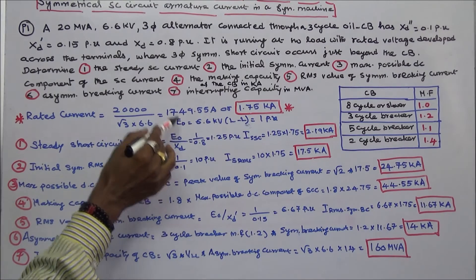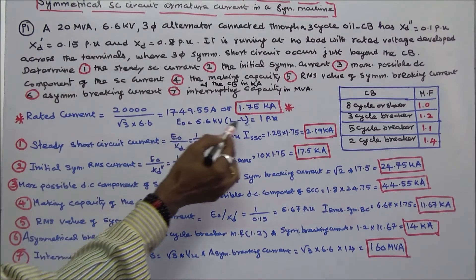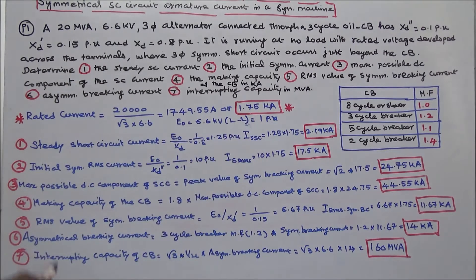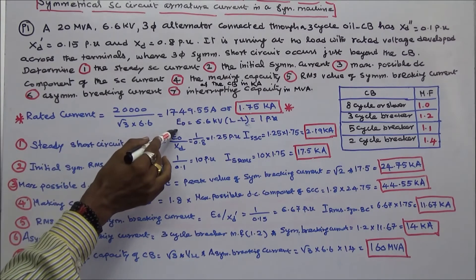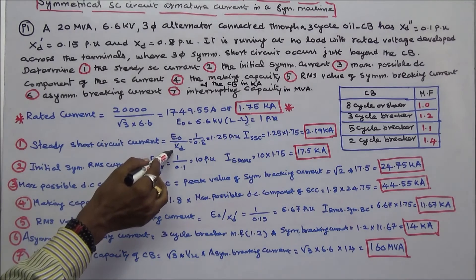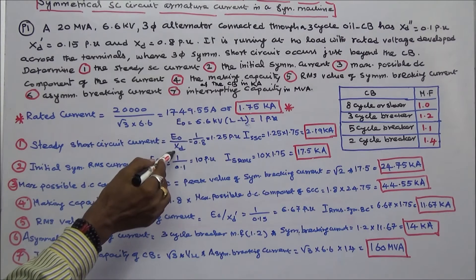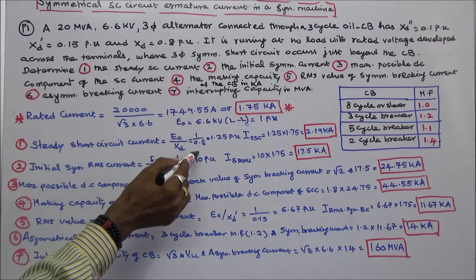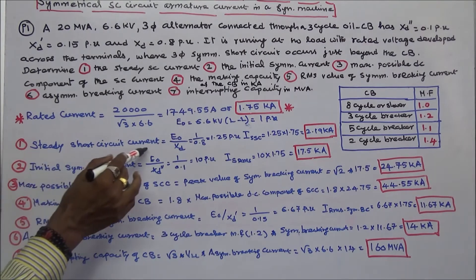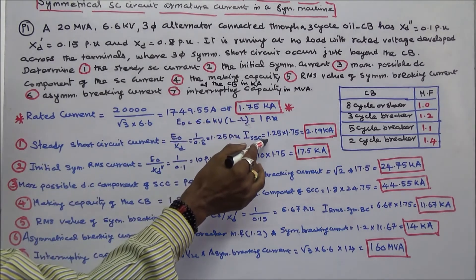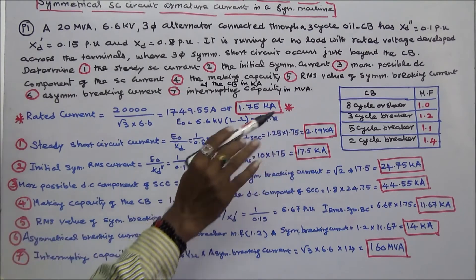E0 is given as 6.6 KV line-to-line voltage, so E0 equals 1 per unit. First, the steady short circuit current equals E0 divided by XD (steady state reactance). E0 is 1, XD is 0.8, so 1 divided by 0.8 equals 1.25 per unit. Actual steady short circuit current is 1.25 into 1.75 kA, which equals 2.19 kA.